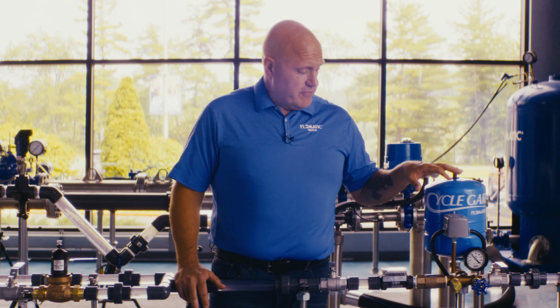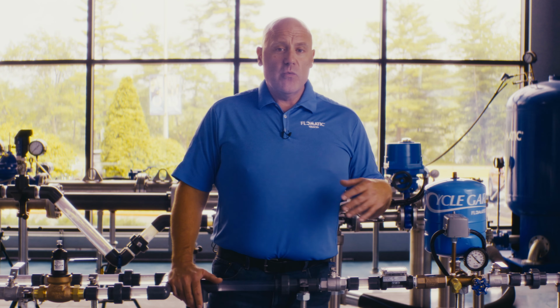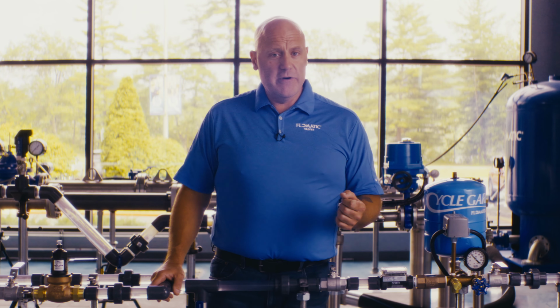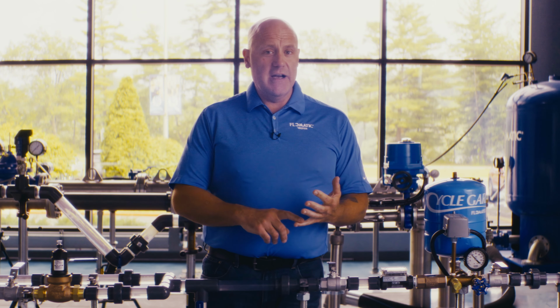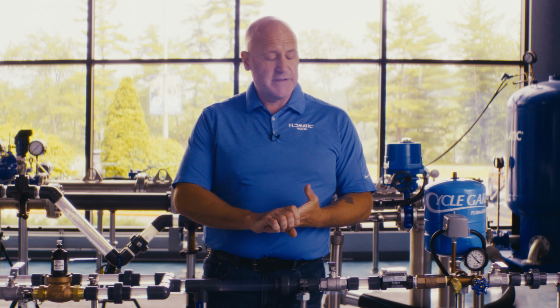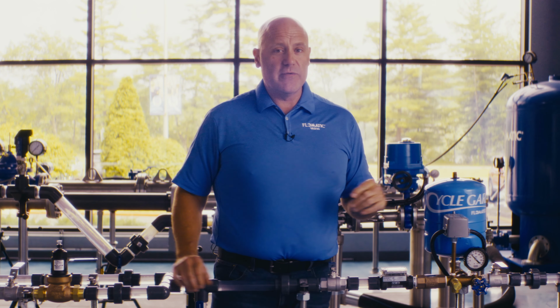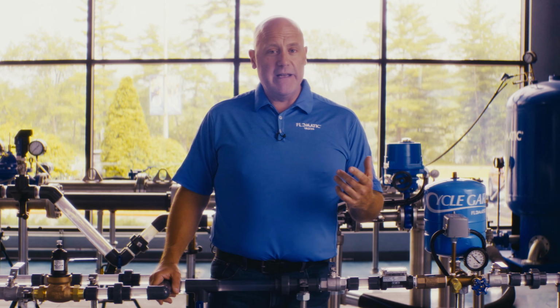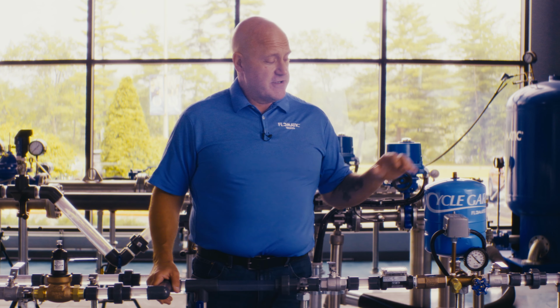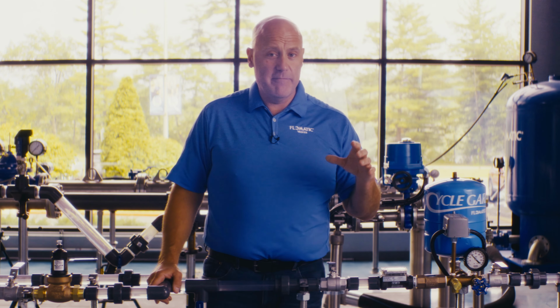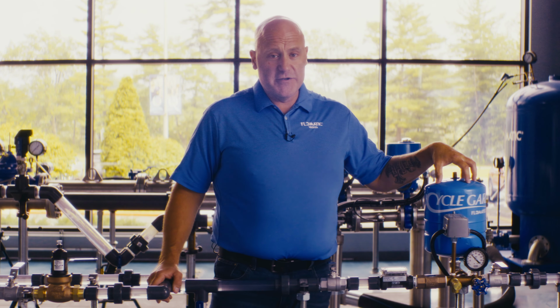I had referenced how upon install, it's very important to make sure things are set correctly. With our larger units that we don't show in this working demonstration, it is also important to take into consideration your tank size, your switch settings, your pressure relief settings. They will require larger tanks. If we have a larger, let's say 2-inch Cycle Gard CI squared, used maybe in a very large home, a restaurant, maybe it's being used for irrigation, it will be necessary to have a larger tank. Something of that nature with a high pump output is going to require a larger tank.